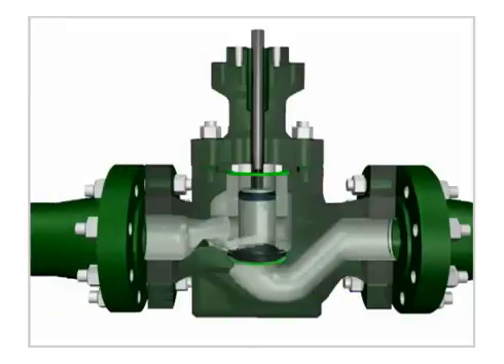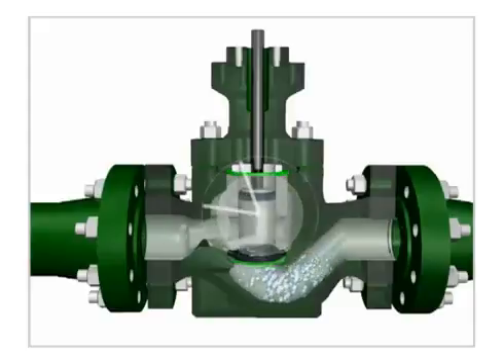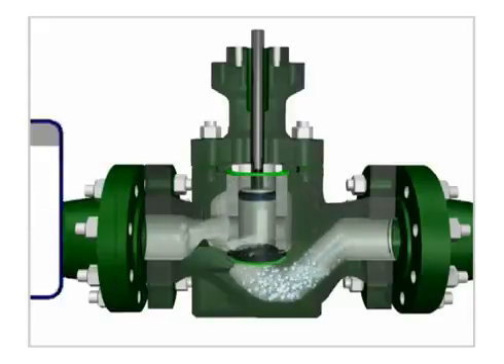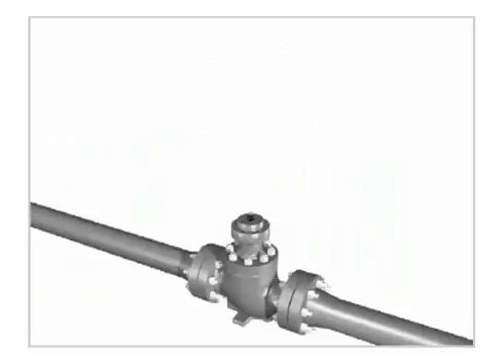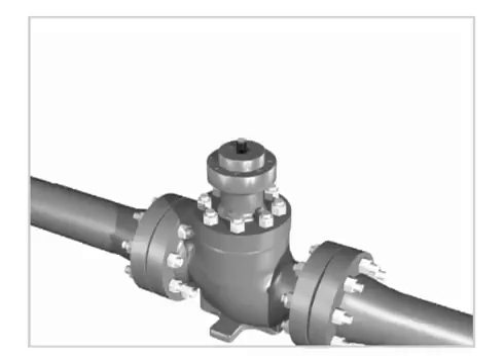The length of exposure to cavitation. The more frequently that cavitation occurs in an area, the more likely it is to sustain damage. Valve size. Increasing the valve size tends to make the effects of cavitation worse.